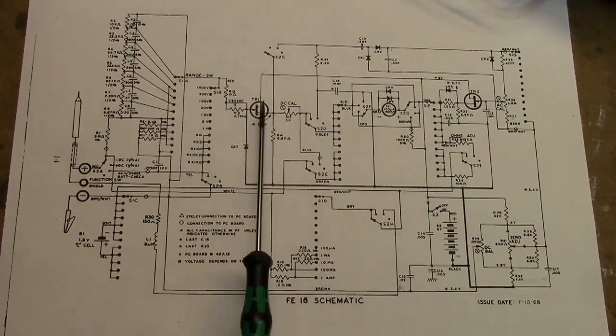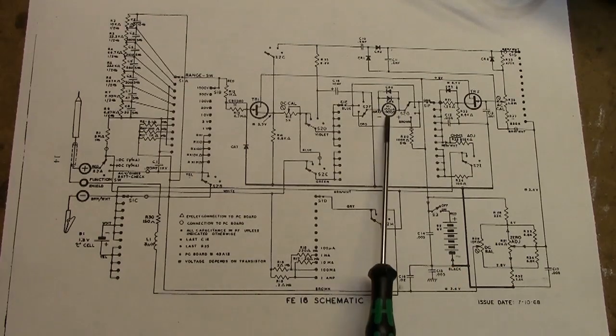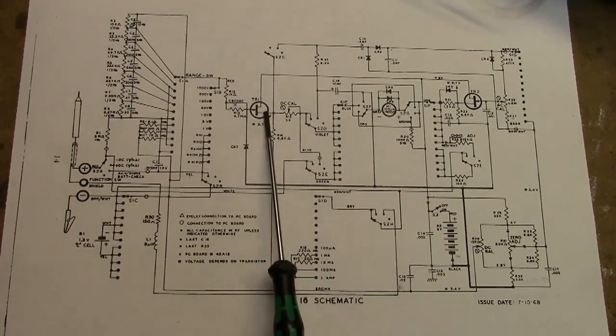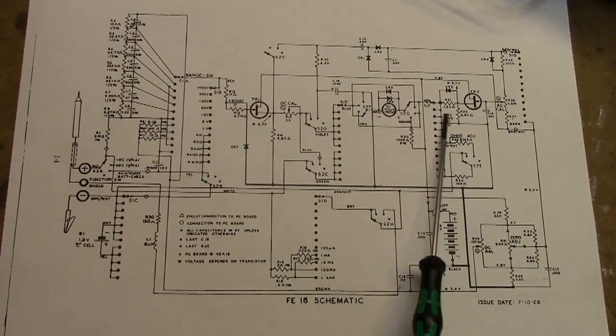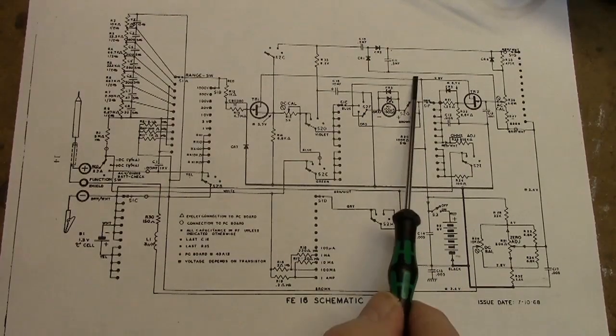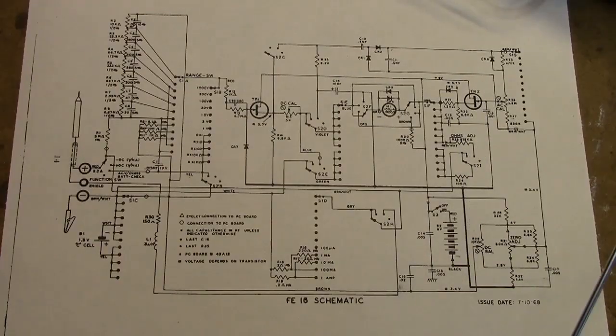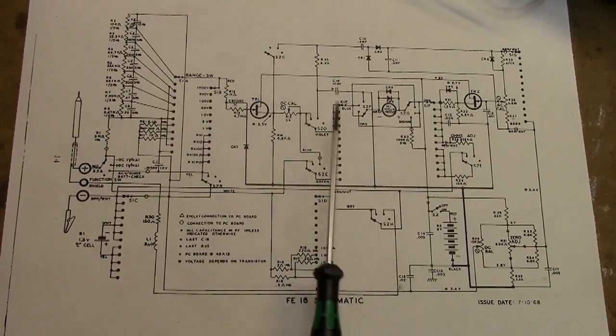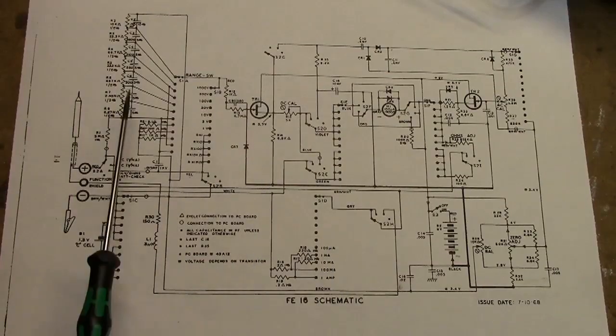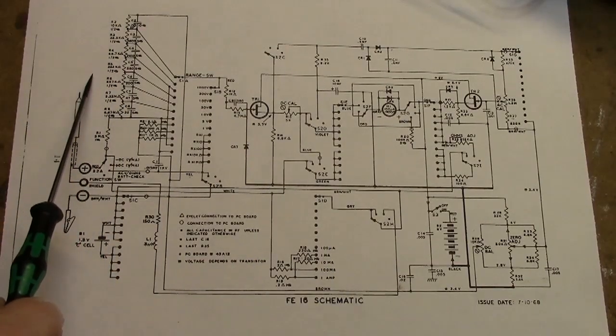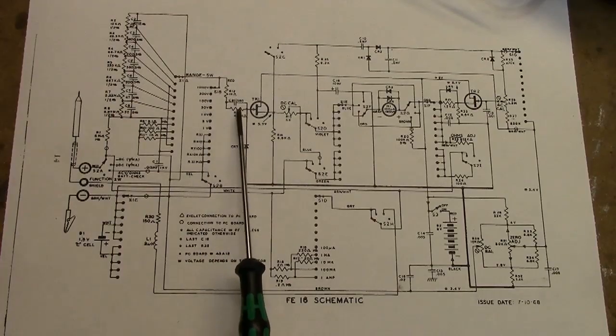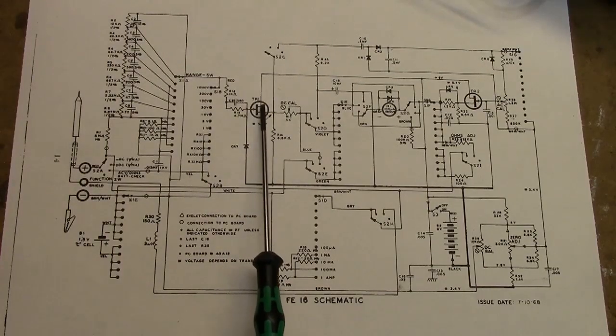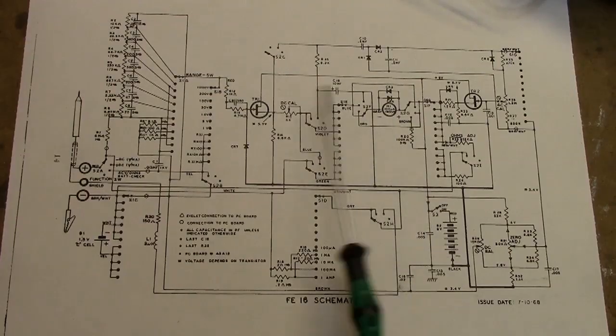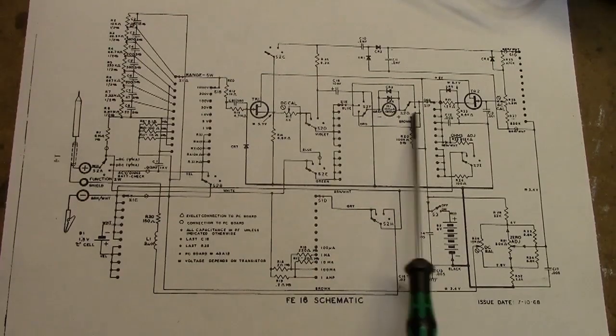Now these 2 FETs form a differential pair here, and here you can see the meter in the middle is connected through the sources here. They're fed a common voltage here to the drains. So anyway, when you balance this out, once you connect an external voltage, for example, that will change the gain of this stage here, and that will unbalance the differential pair, and then you'll get a meter indication. And then by switching in various multipliers here, you can get different ranges.